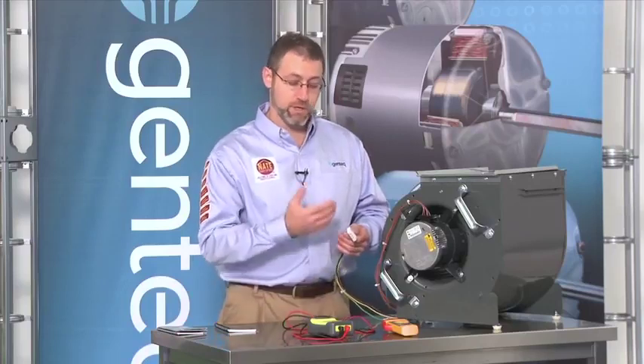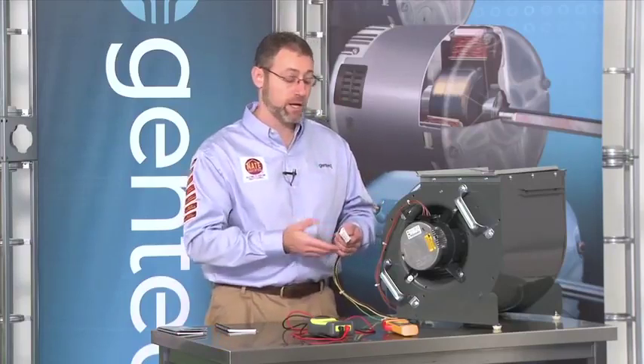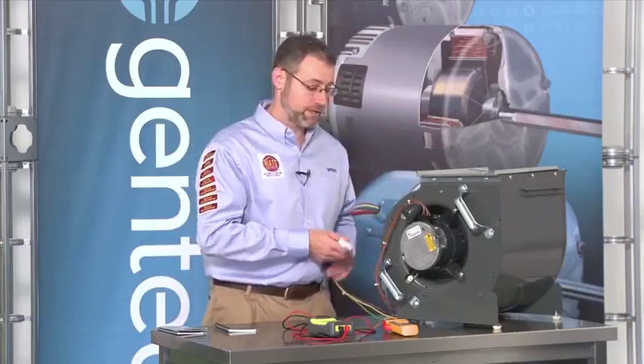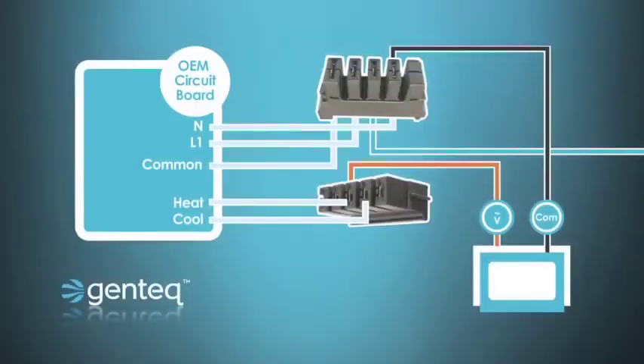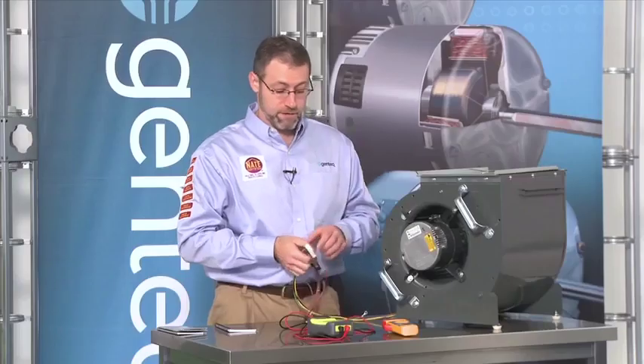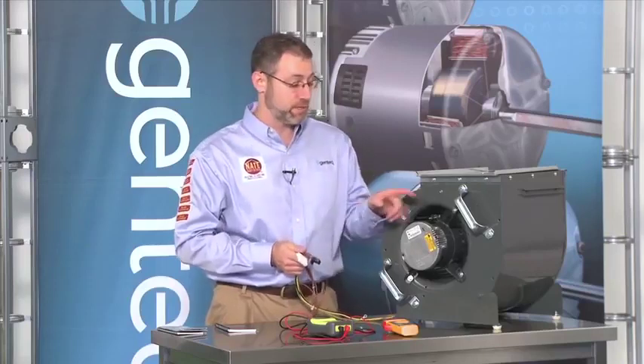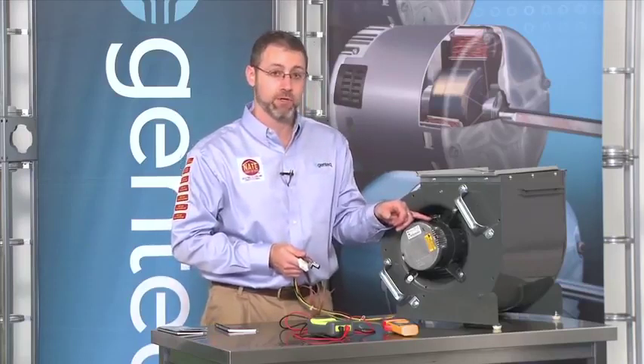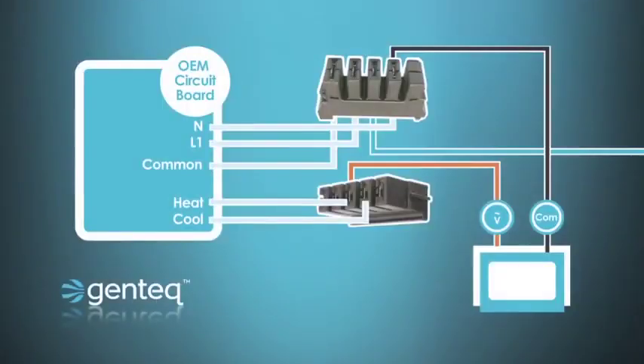So once we've confirmed that we have high voltage on this plug, we would then turn the power off again, and now we can troubleshoot the low voltage plug. So again, power is still off, so we're disconnecting the low voltage plug. If the manufacturer did not use a high voltage plug, they used flying leads on that portion, I could just take the common wire out. So what I'm going to do is I'm going to be taking my meter and checking from the common in the high voltage plug and the 24 volts that will be coming to pins 1 through 5.